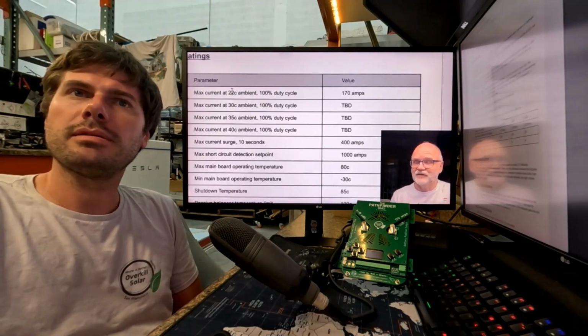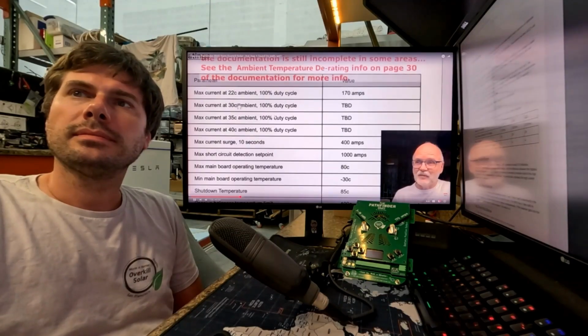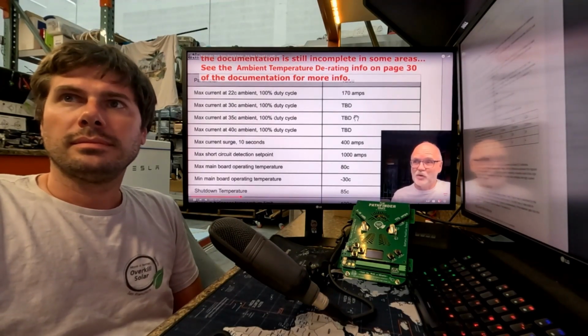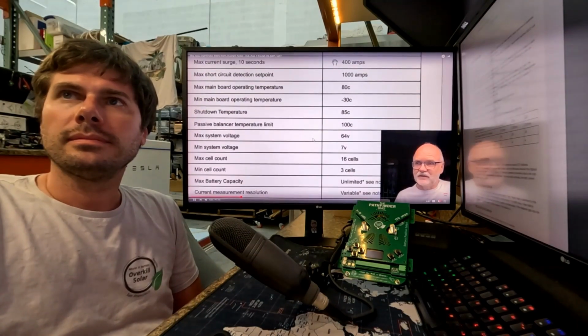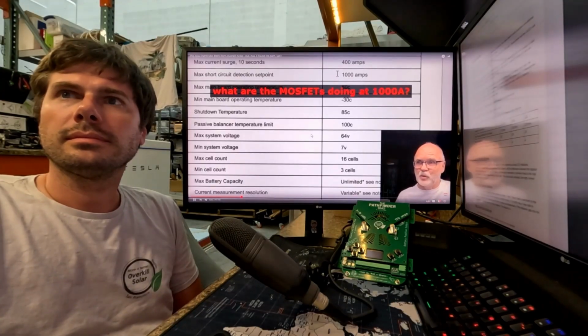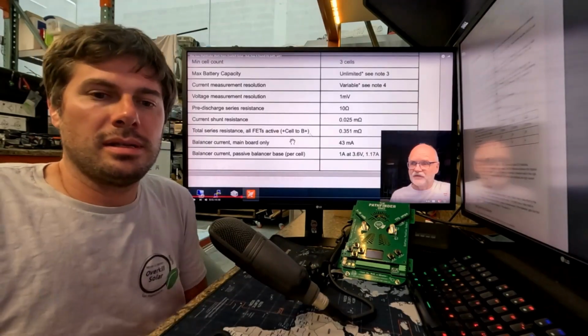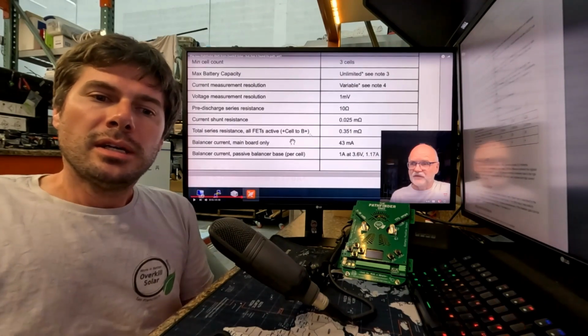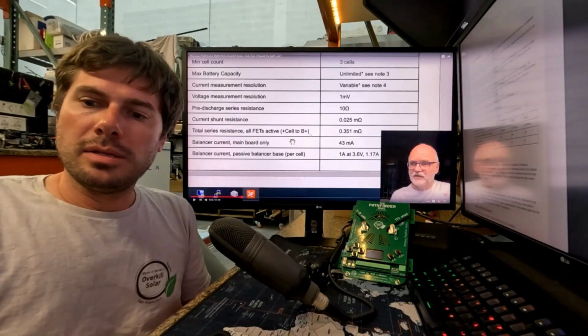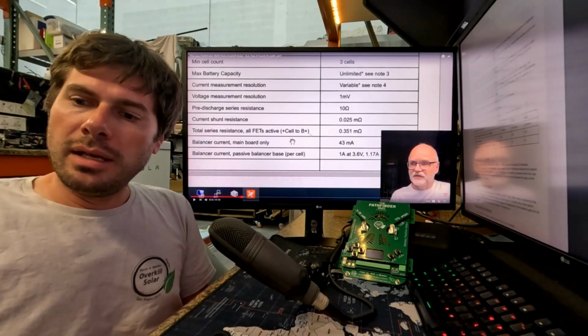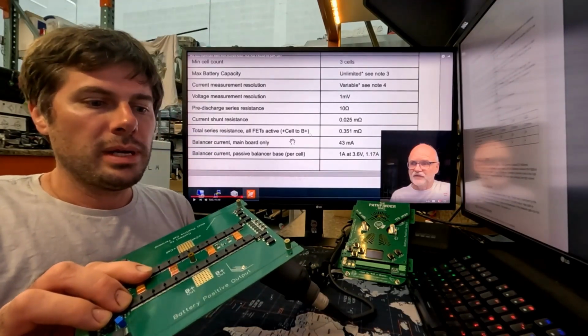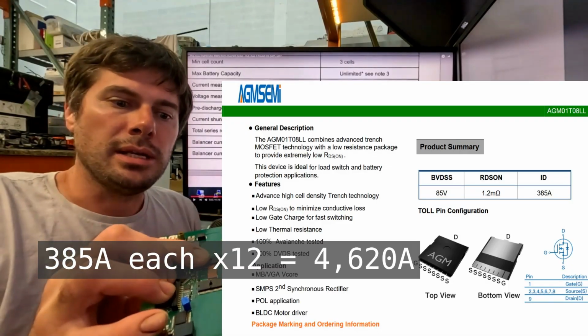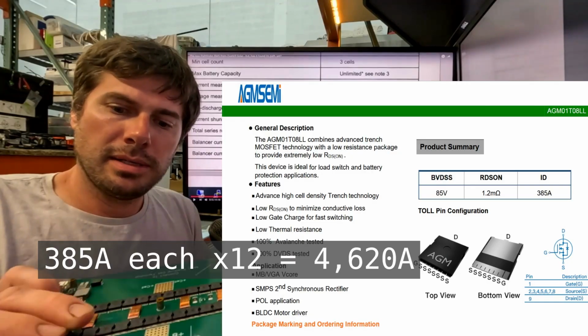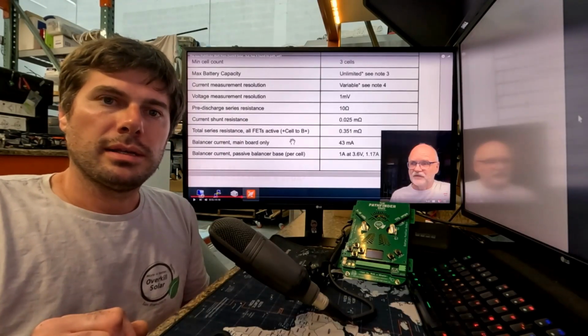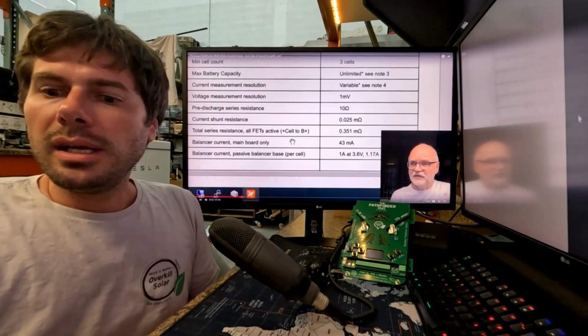170 amps at 22 degrees Celsius, and as I said before, that's a 100% duty cycle - everything warmer is to be determined. So obviously the current goes down the hotter the BMS gets. 400 amps maximum surge current for 10 seconds, and 1000 amps short circuit detection point. Actually, the MOSFETs don't have any trouble handling 1000 amps - the current limitation on the complete BMS assembly is just based on temperature. Each one of these has a nominal rating of about 600 amps with adequate cooling, and there's 12 of them in 2 banks, so 1000 amps for a few seconds - or in this case only a few microseconds - is not a problem at all.